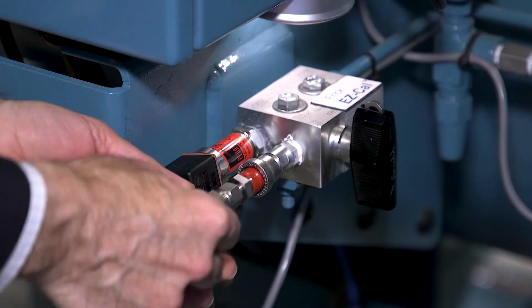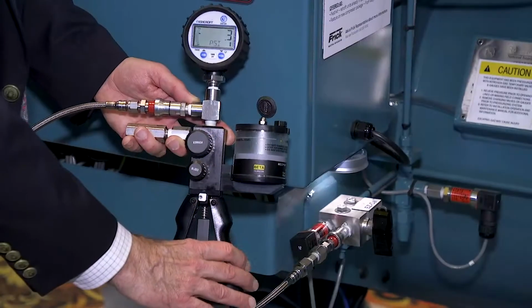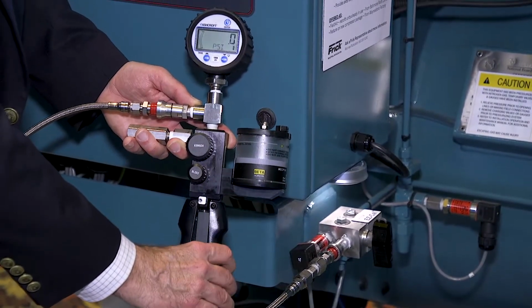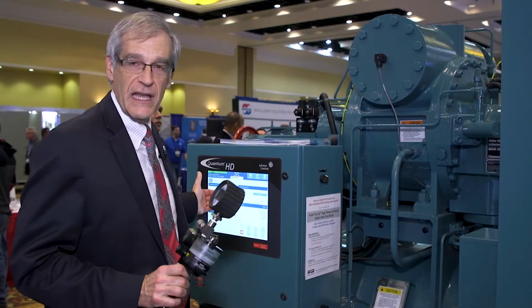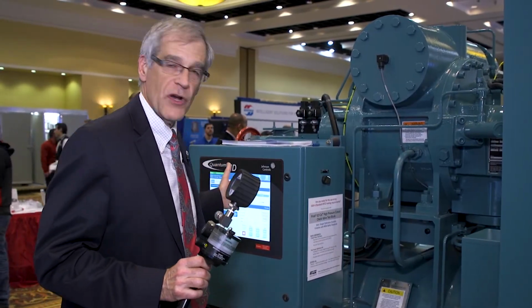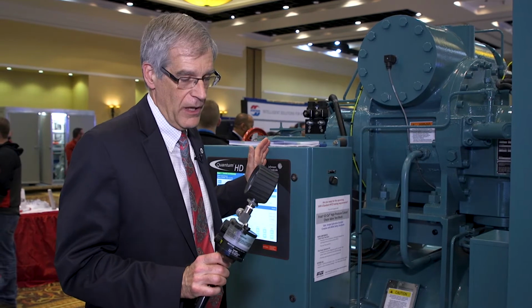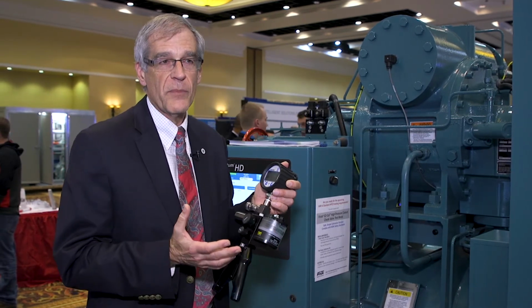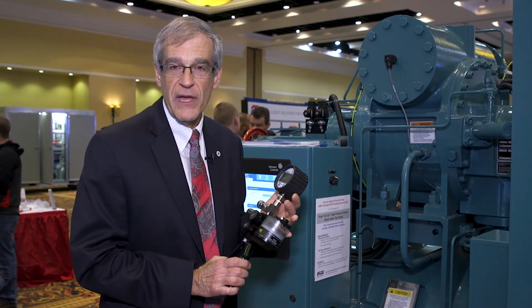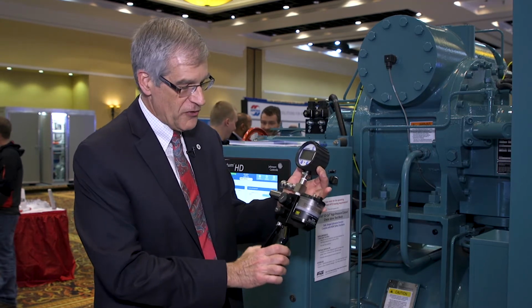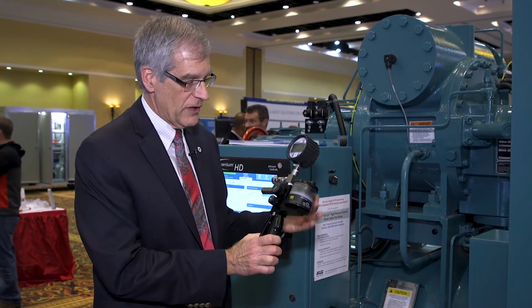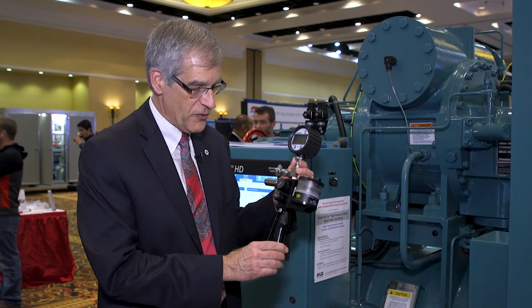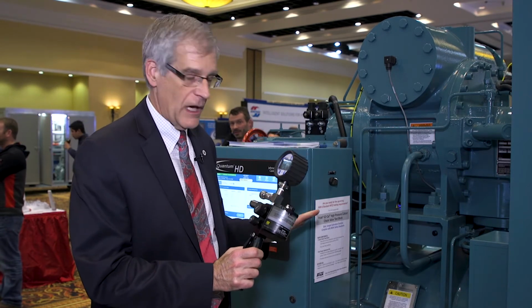I will connect my pump with the hose, and I begin raising the pressure on the high pressure cutout with the pump. I will take it up to the point where the high pressure cutout will approach the pressure I'm desiring, typically on an ammonia plant, probably 225 psi. As I get closer, I can change the stroke length on the pump, so it's a very small stroke, and I can come in very close to the cutout pressure.